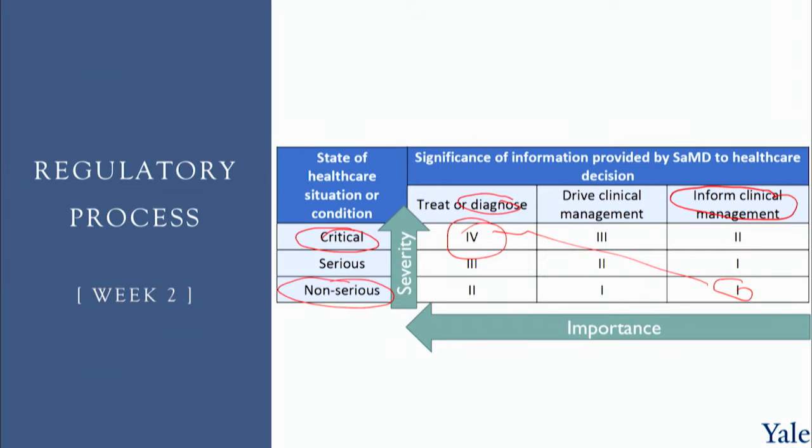And this affects everything we will talk about. So the risk classification of the software defines the rest of the process. And we'll come back to risk classification multiple times. They're slightly different systems, 1 to 3, 1 to 4, A, B, and C, but the fundamental principle is the same. Low risk, low requirements, high risk, high requirements.